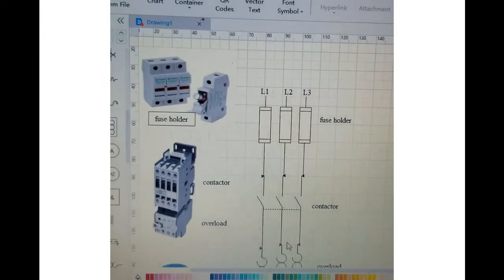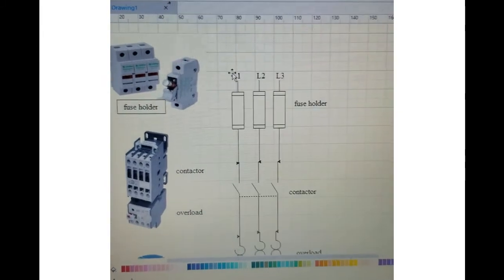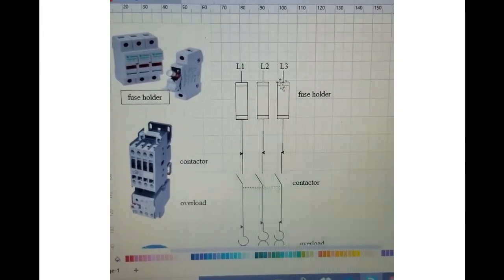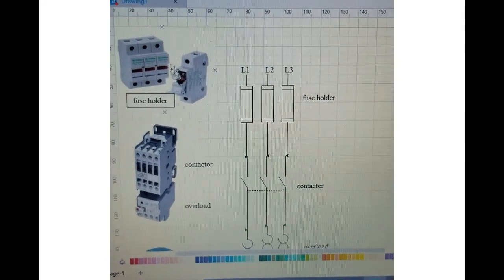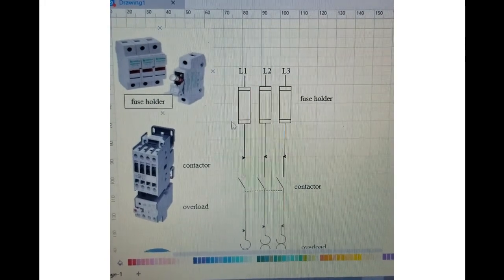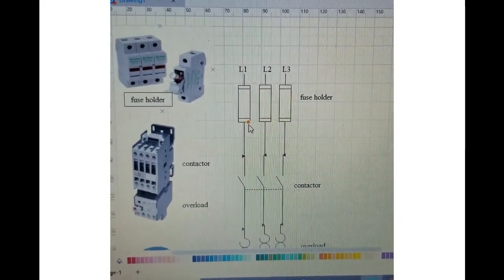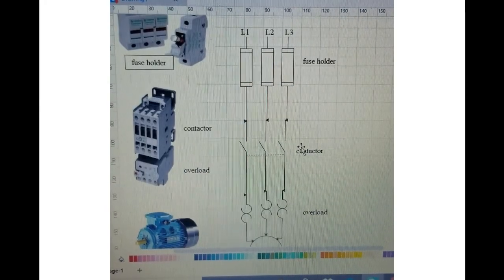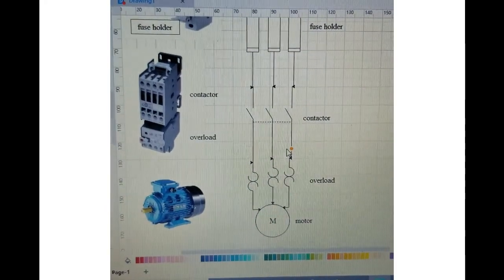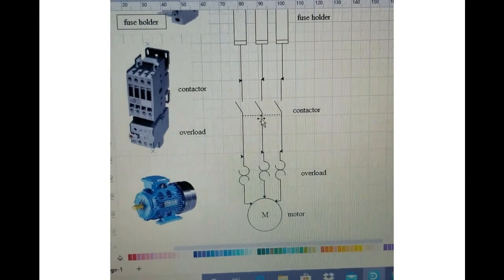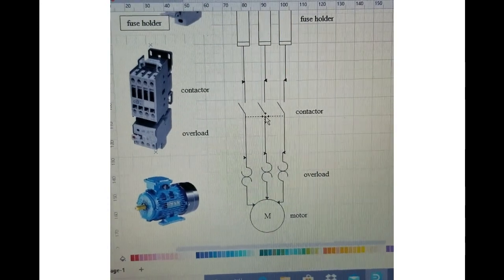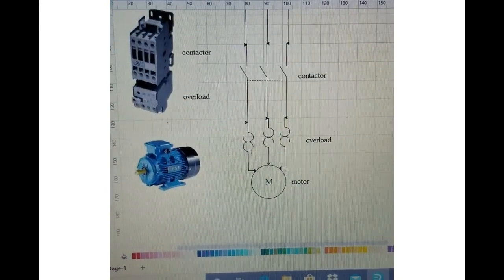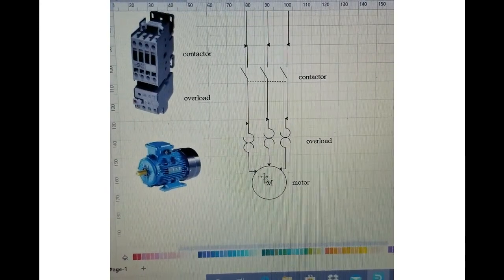So basically how this thing is functioning is this: we have three phases L1, L2, L3 coming on top of our fuses, then they're coming out from the bottom of the fuse going on top of the contactor, and then it is passing through the overload, and after passing through the overload it's going on the top of the motor.